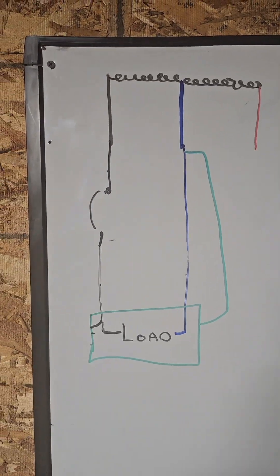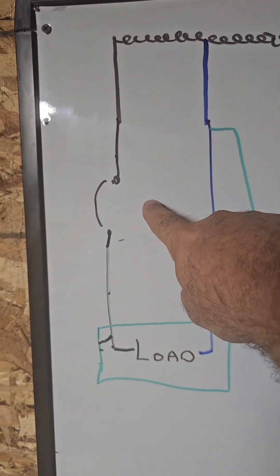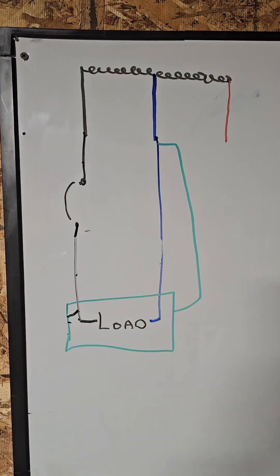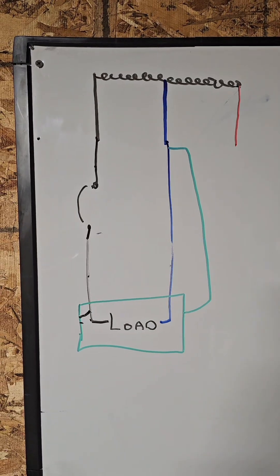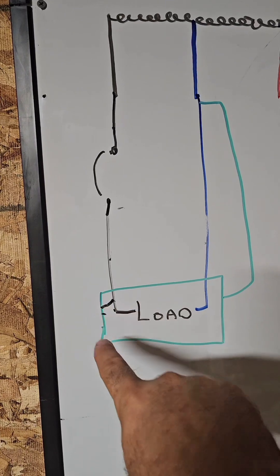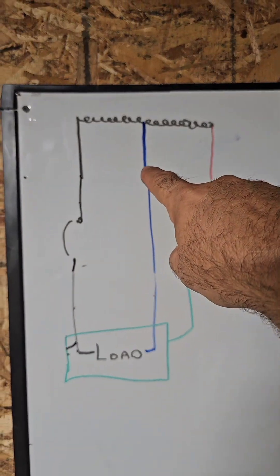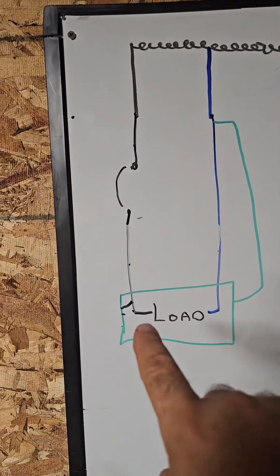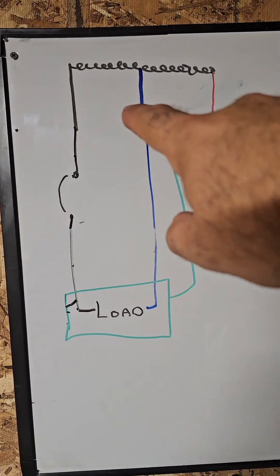So now, because this can be a fuse or a circuit breaker, the code refers to it as an overcurrent device. Now, is it clear that the fault path is from the fault point on the circuit back to the electrical source? Not back to the earth, not back to the dirt. It's from the fault back to the source. So the term the code would use is to clear a fault is to facilitate the opening of an overcurrent protection device.